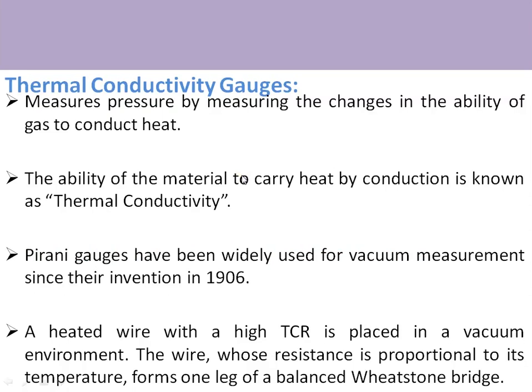A manometer is a direct pressure measurement technique where force caused by pressure is measured in terms of liquid head. At lower pressures, direct measurement is not possible because the force is insufficient to generate a measurable head. Therefore, indirect pressure measurement is used. As per the kinetic theory of gases, gas has the ability to carry heat, has viscosity, and its molecules can be ionized so that ion current can be measured. Any of these properties can be used for measuring lower pressures.